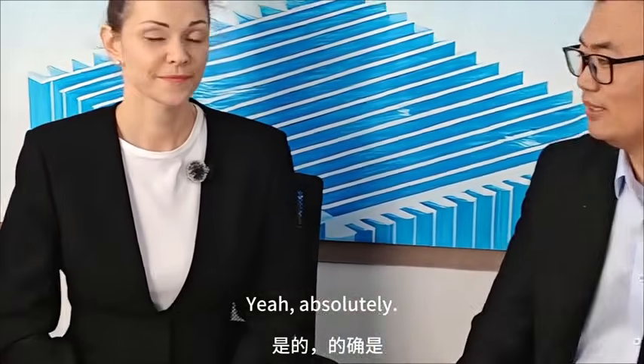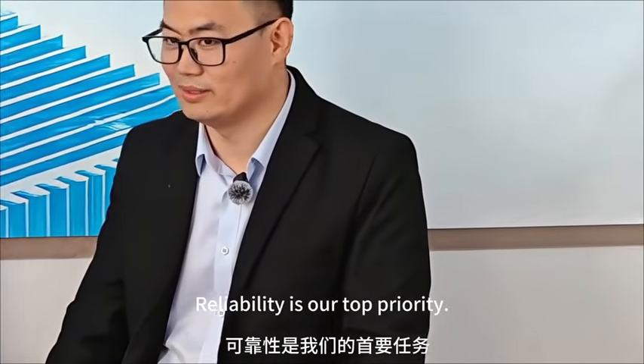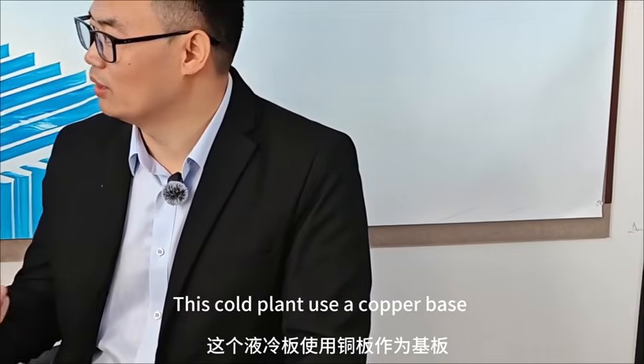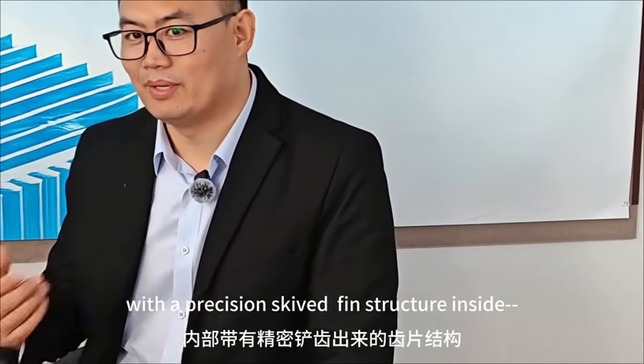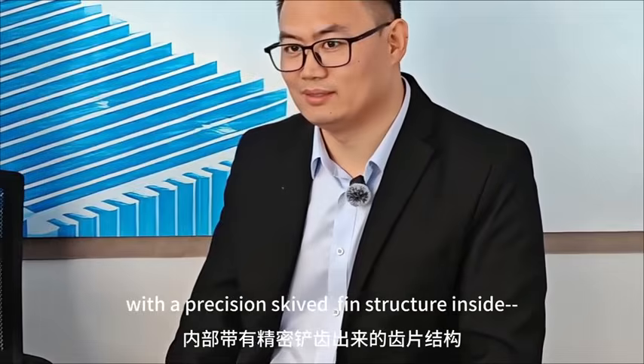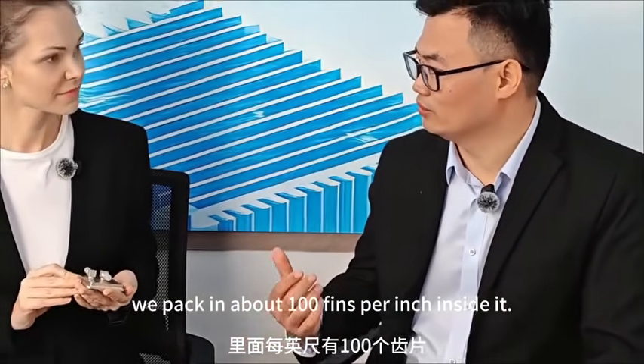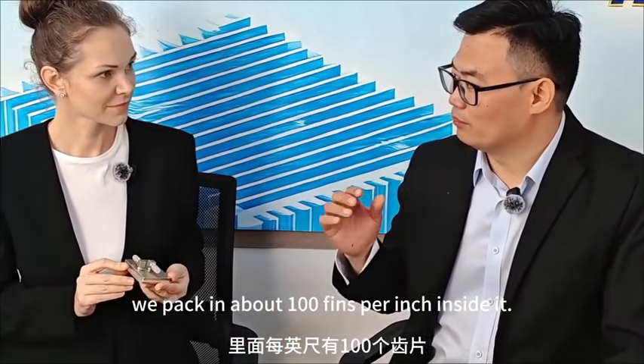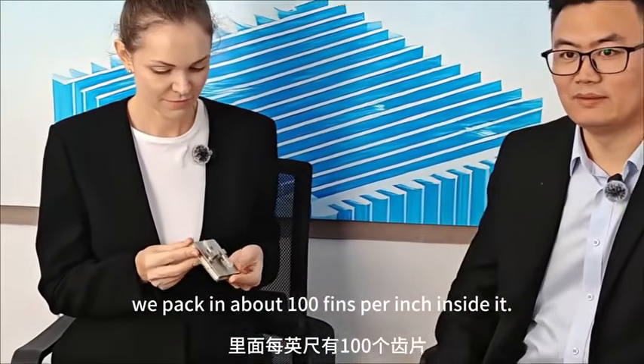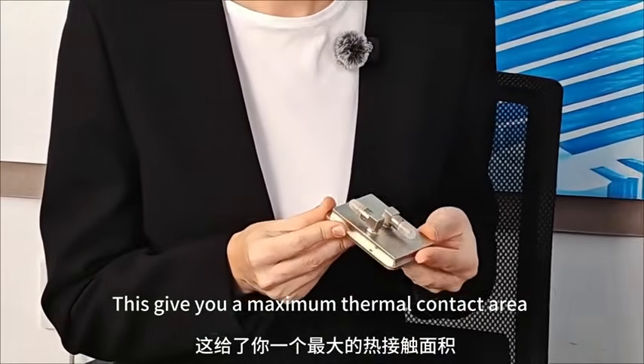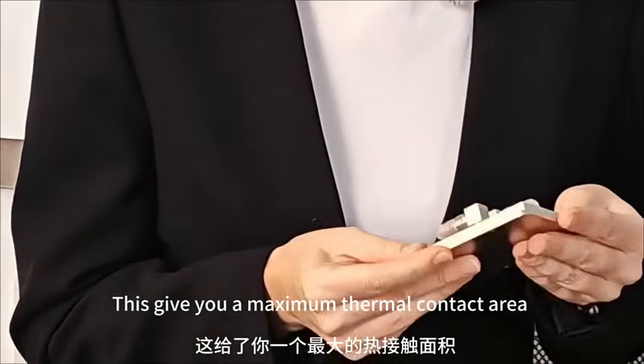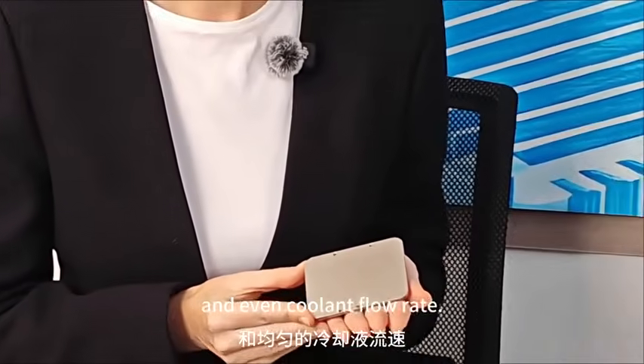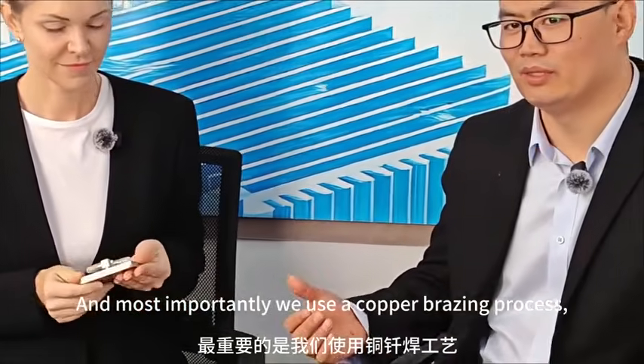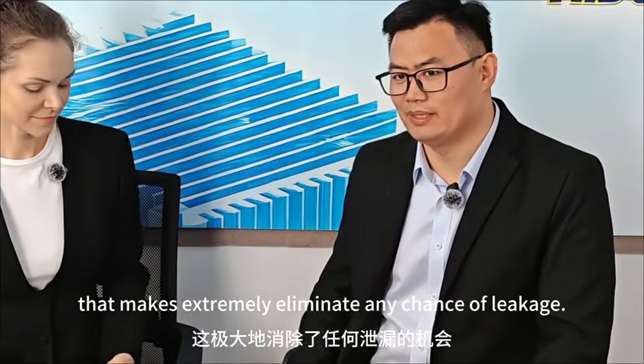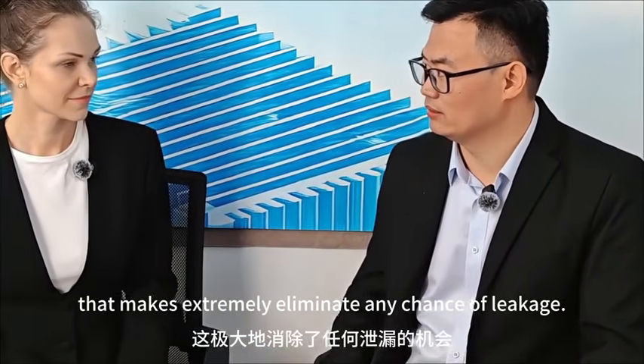Yeah, absolutely. Reliability is our top priority. This cold plate uses a copper base with a precise skived-fin structure inside. We pack in about 100 fins per inch, which gives maximum thermal contact area and even coolant flow rate. Most importantly, we use a copper brazing process that eliminates any chance of leakage.